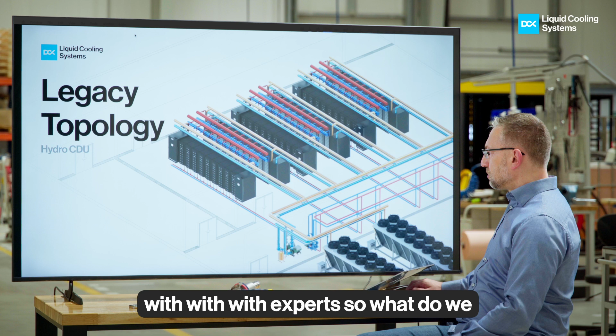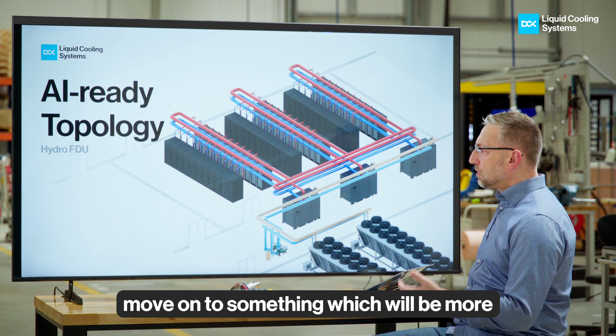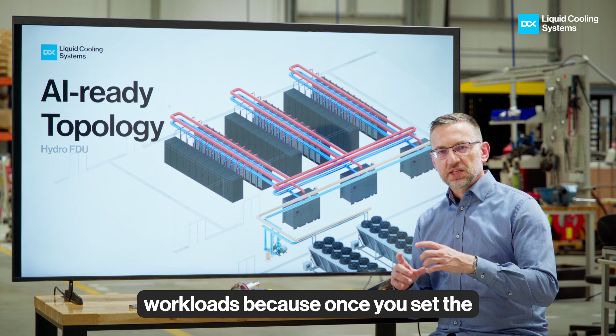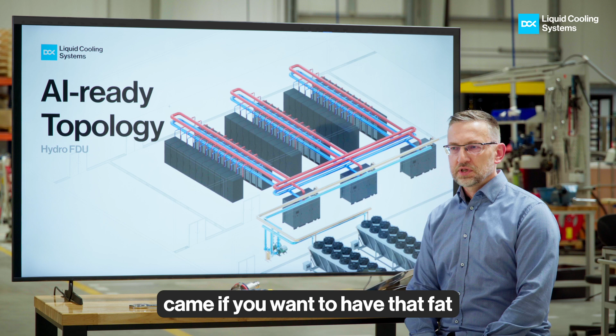What we suggest is to resign from that topology entirely and move on to something more appropriate for AI workloads, because once you set the pipe and pipe diameters, you're set with all those pipes for the foreseeable future. You don't want to rip everything out in 2 years because new GPUs came out. If you want that fat contract from a major AI hyperscaler, you need to provide a solution that will last for years - 5 to 10 years, not just 2 years.